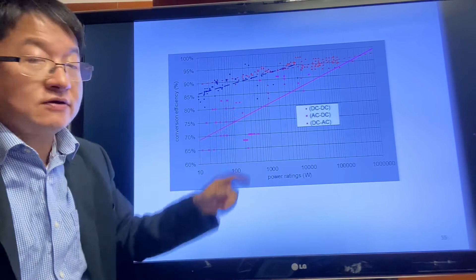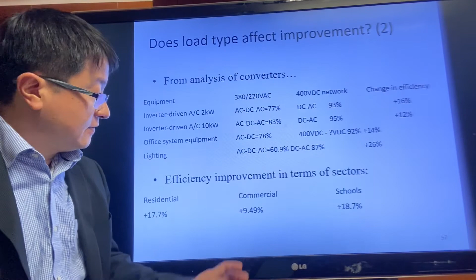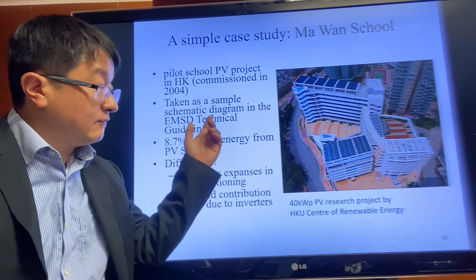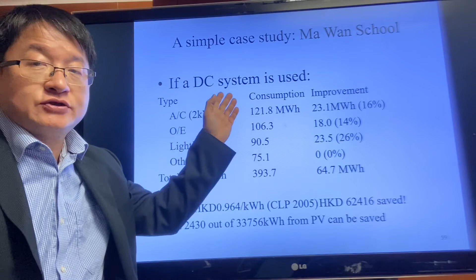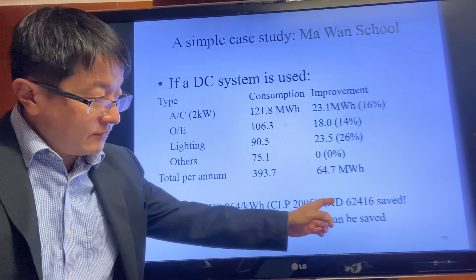So we also studied the efficiency improvement of this DC distribution network, and the efficiency improvement in terms of different sector is as follows. For residential is about 17%, for commercial is 9%, and then for school is about 18%. And one of the school in Hong Kong, in Ma Wan, is also installed with the PV system, and then the distribution system in this building is a DC network. So we have also conducted an analysis in this school if they change this distribution network into DC, and the overall saving in a year could be around 62,000 Hong Kong dollars.